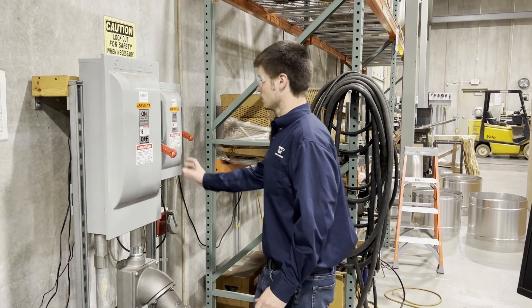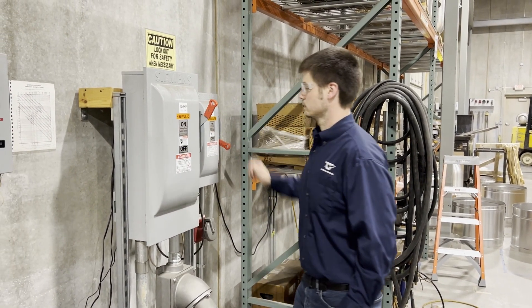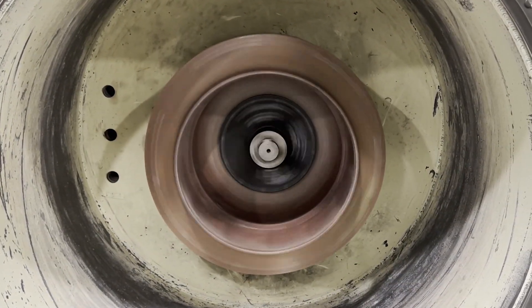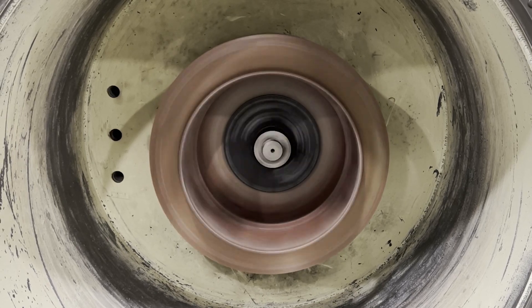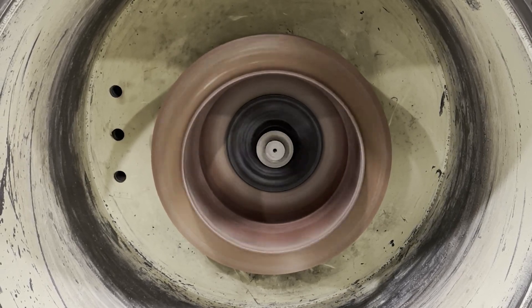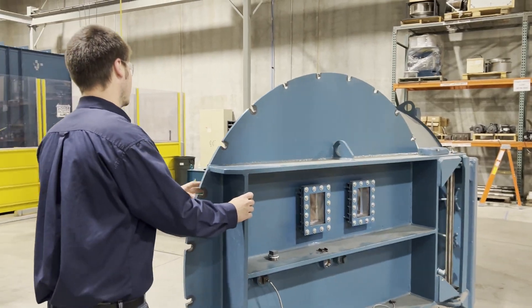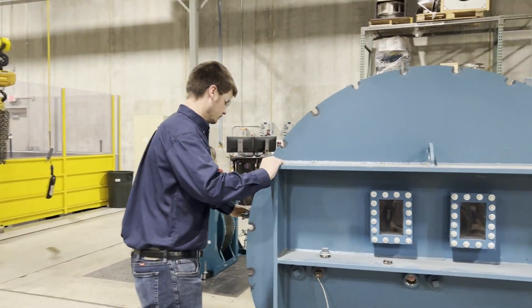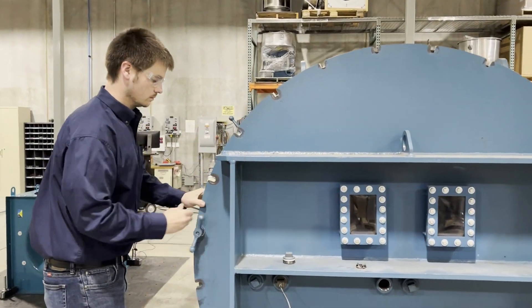A catastrophic failure is never a fun thing to have, and that's why we do overspeed testing in the lab. The goal of overspeed testing is to make sure that we don't deform the material — we don't want to bend the metal beyond its limit. It needs to stay within its allowable stresses so that we don't have accelerated fatigue failure or catastrophic failure of parts coming apart. It's a requirement in the engineering development process to ensure those things don't happen out in the field.